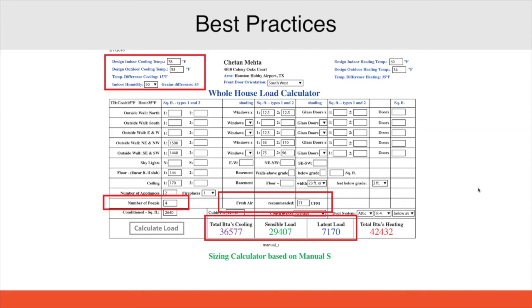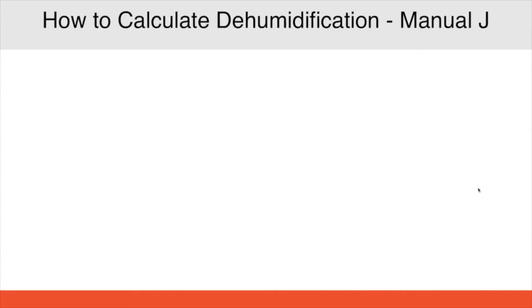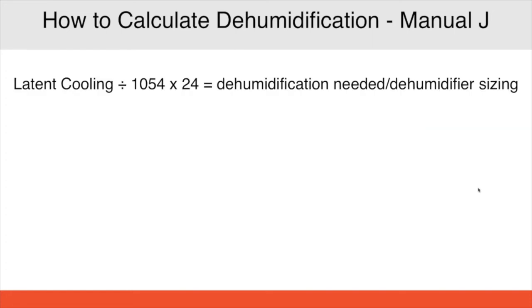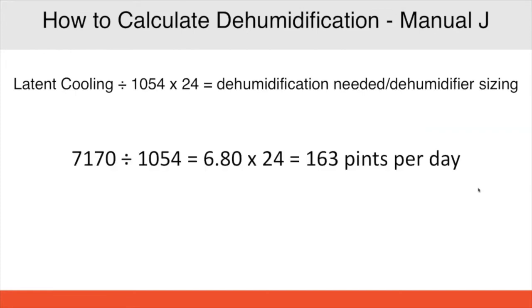So 7170 is our latent load. So based on Manual J, how do we calculate dehumidification? The latent cooling, which is our 7170, is going to be divided by 1,054, because it takes 1,054 BTUs to remove 1 pint of water, and we're going to times that by 24 hours in a day, and that's going to give us our dehumidifier sizing. So again, that's 7170 divided by 1,054, and then we're going to times that by 24 hours a day, and that's telling us that we need 163 pints per day of water removal.